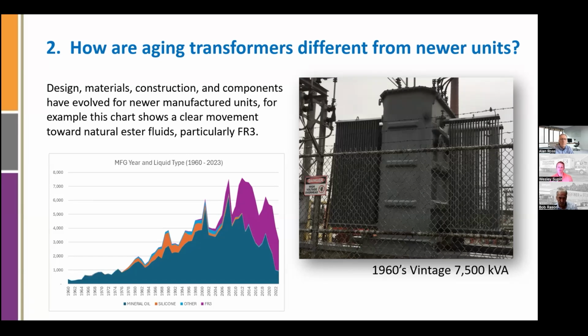And over time, the fluids have changed. So in the 70s and 80s, silicone became a little bit more popular for units that are either indoors or close to buildings. The purpose of that was for fire mitigation. It's got a higher fire and flash point. And then what you'll see is this purple bar start to come in as a proportion of the number of units. And the purple area is showing FR3. FR3 is a natural ester manufactured by Cargill.